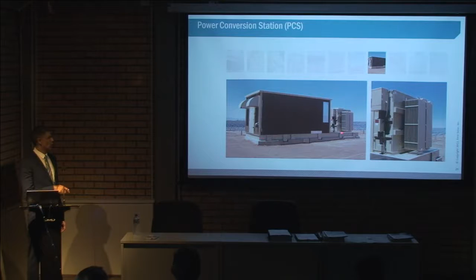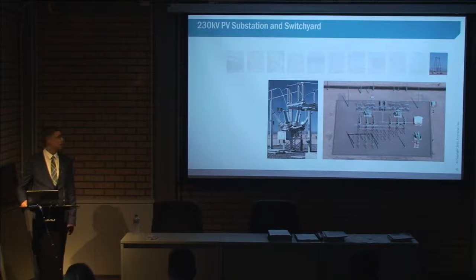This is a power conversion system, a very old one, we don't use that anymore. All power conversion systems are now mounted on a steel skid. We also do a lot of work on substations. One of the largest is a 600 MVA substation in the US, stepping up 34.5 kV to 500 kV with 333 MVA transformers, one of which is a backup transformer.